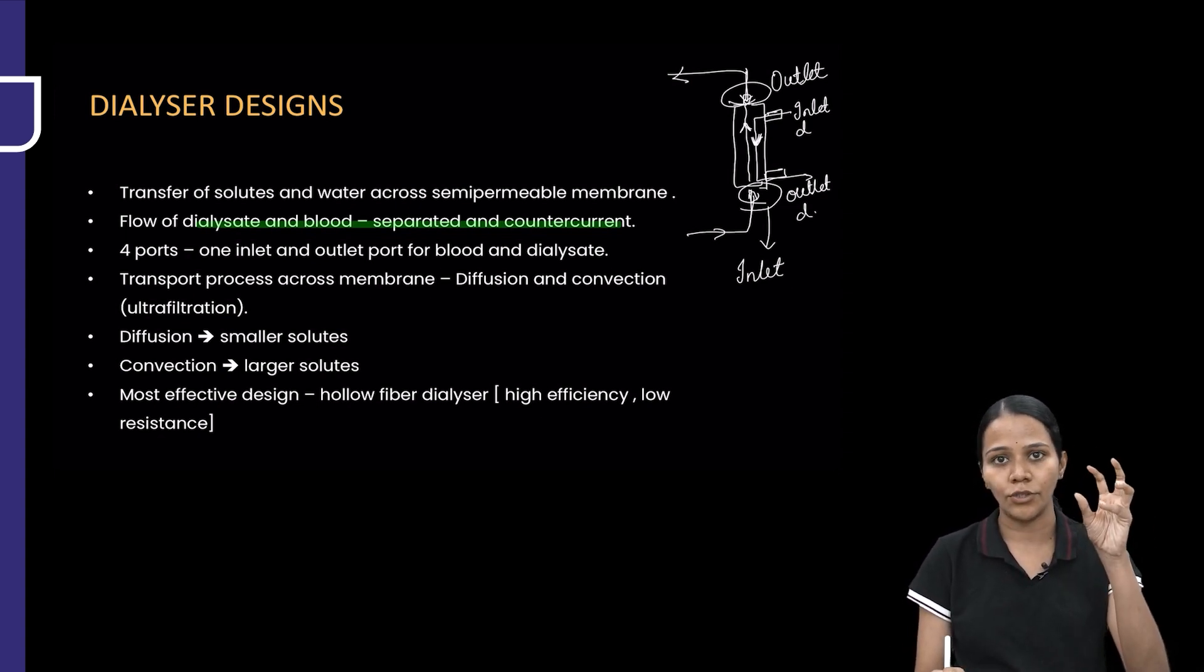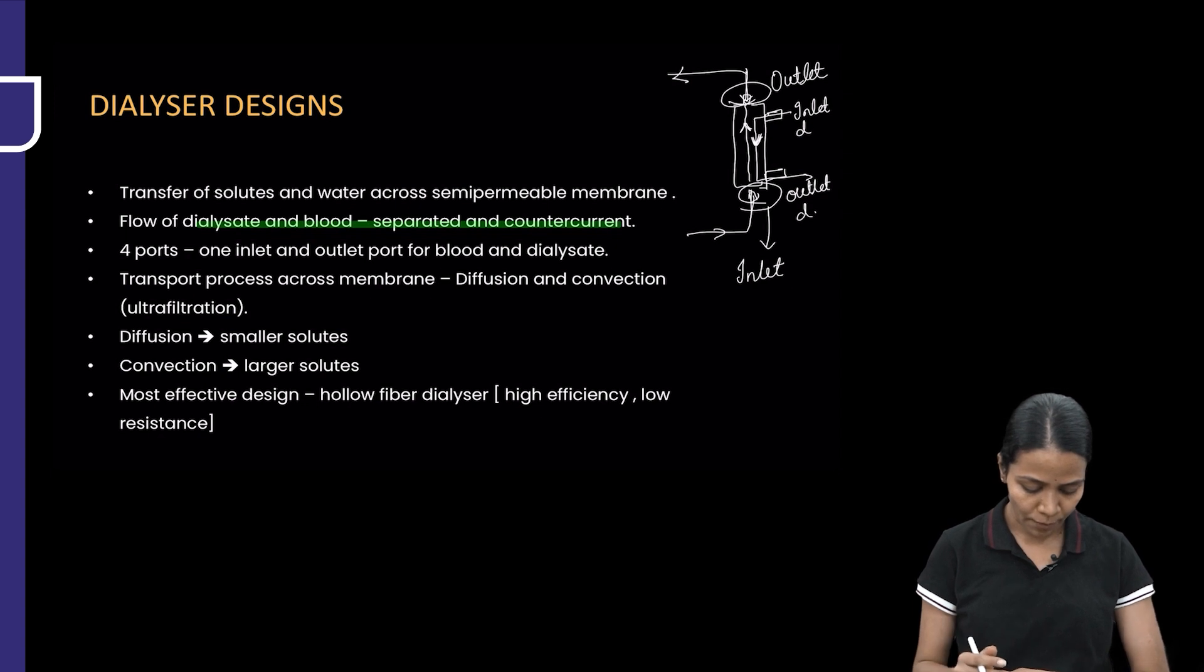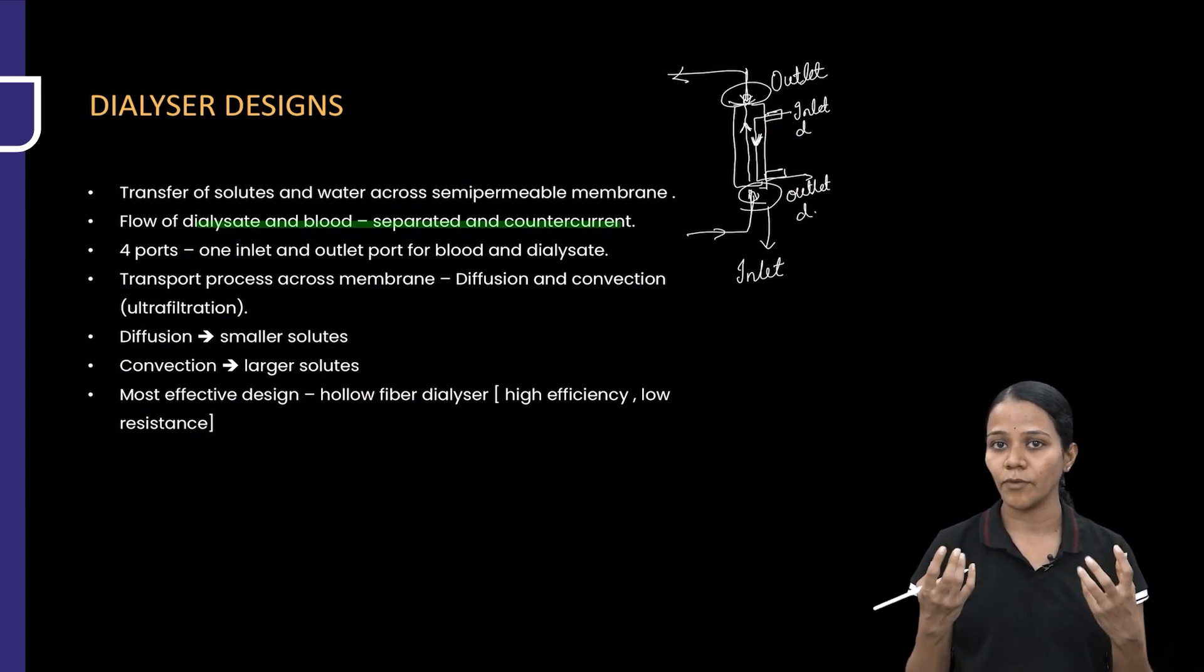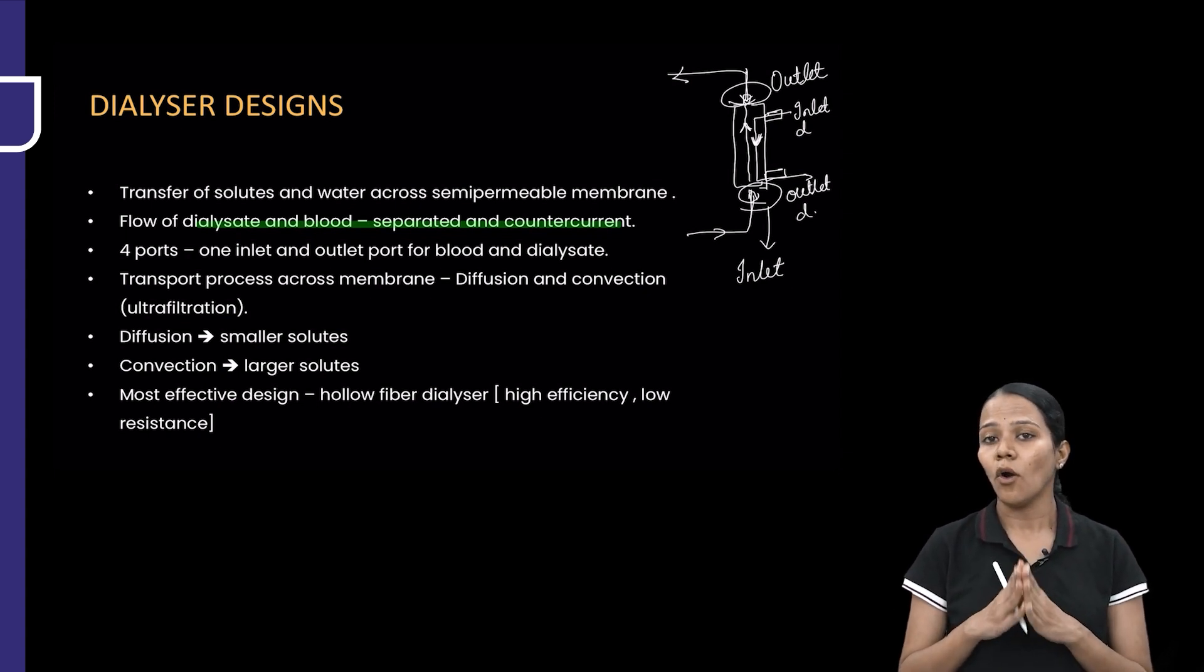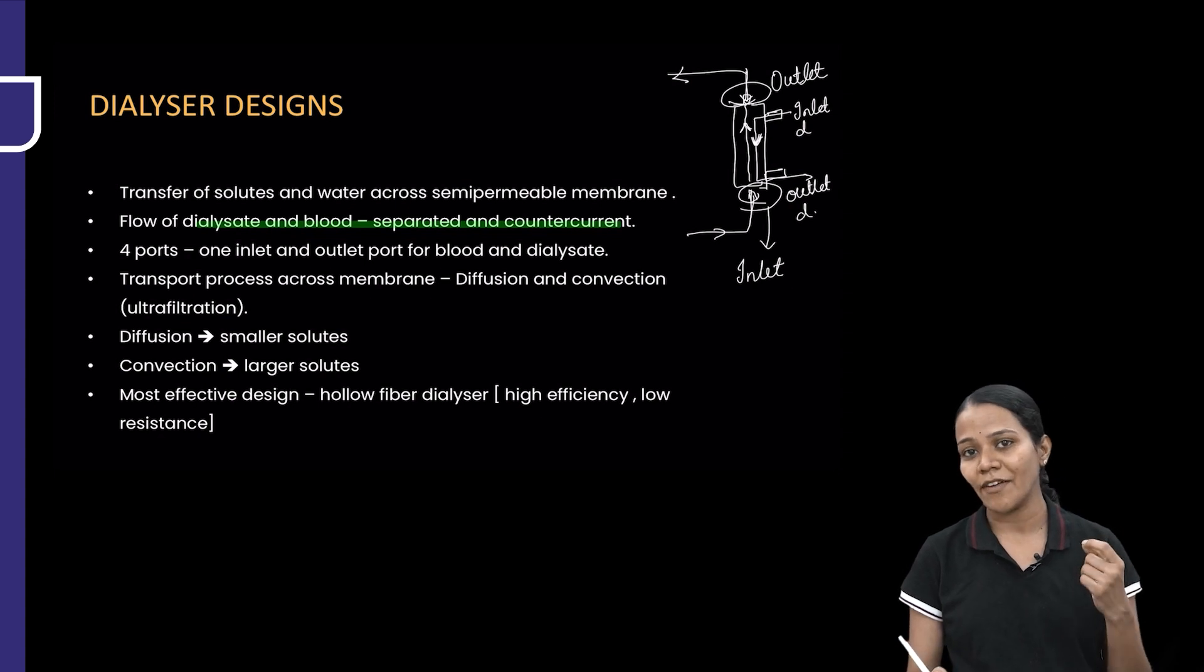Convection is where larger solutes will move along with water through the bigger pores, so that larger molecules are removed. The most effective design is a hollow fiber dialyser. These fibers have high efficiency and low resistance for the passage of blood and dialysate.